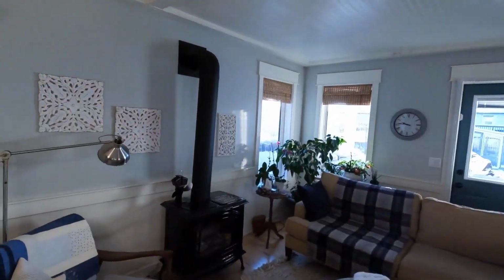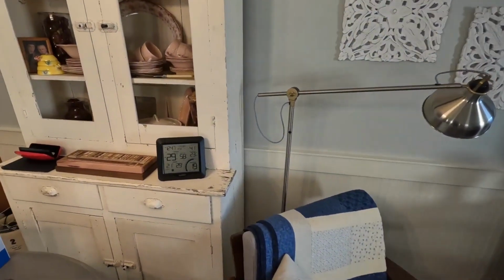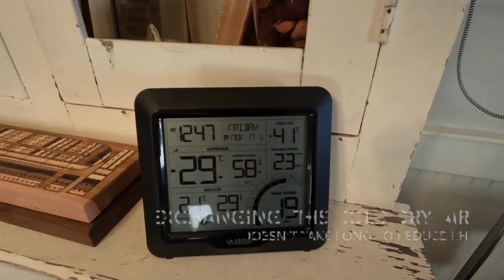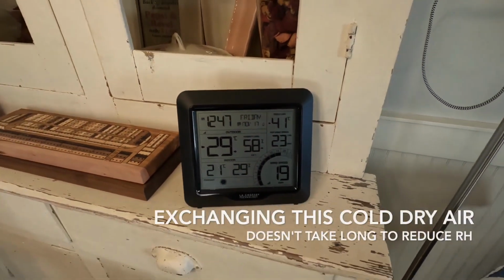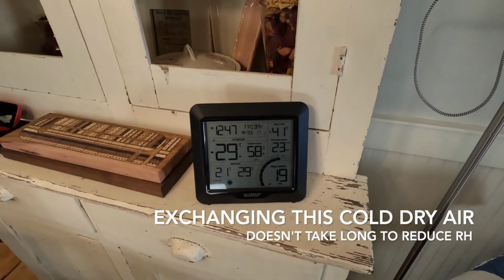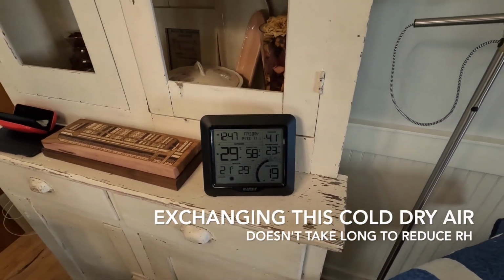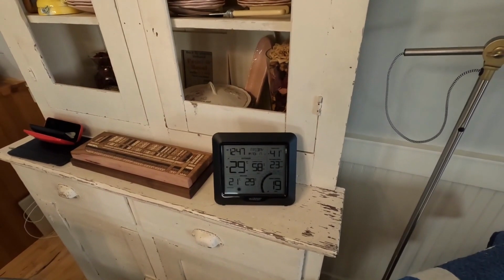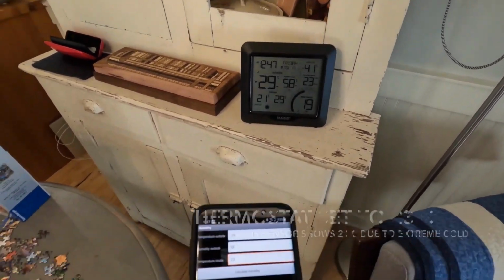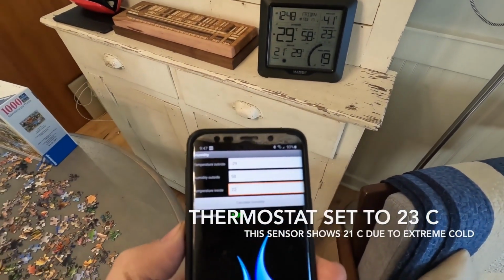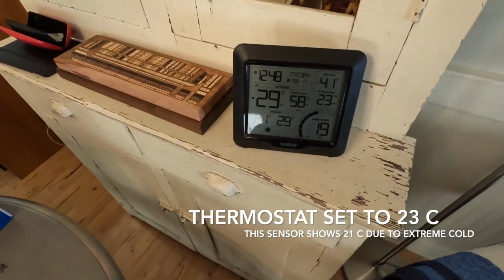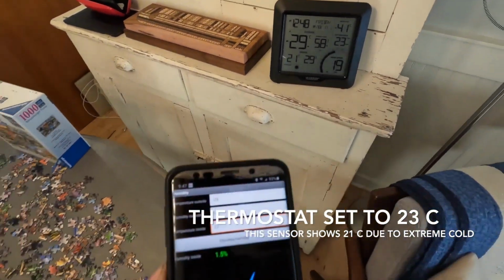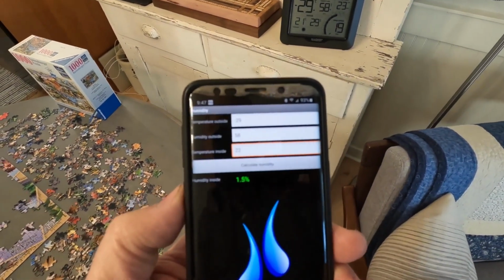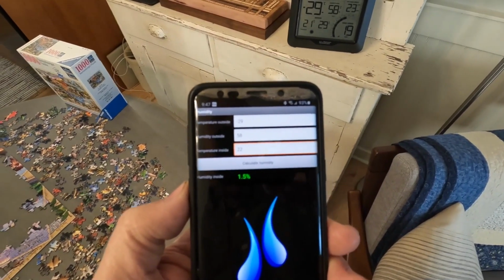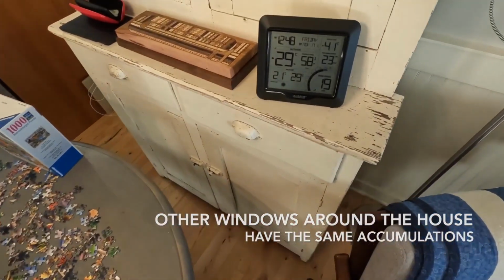This morning it's quite a bit colder than it was yesterday. We've got a minus 29, it was minus 30 just a minute ago, with 58% relative humidity. The wind speed is quite high, so the wind chill outside is minus 45. But when we look at the calculation for relative humidity, if I take that air that's minus 29 and warm it up to 22 degrees inside, I'm at 1.5% relative humidity, so super dry air.